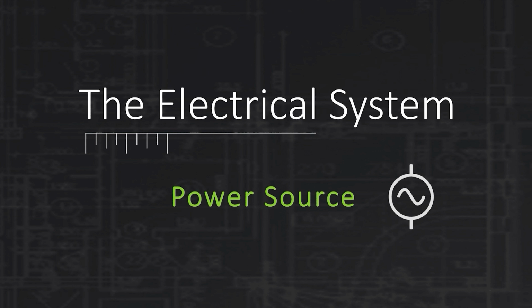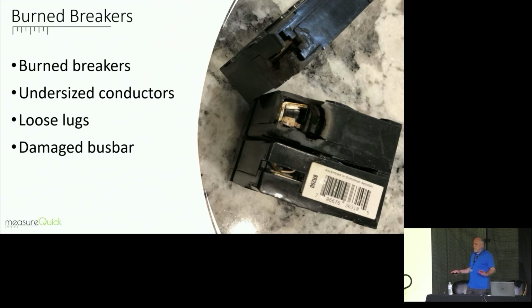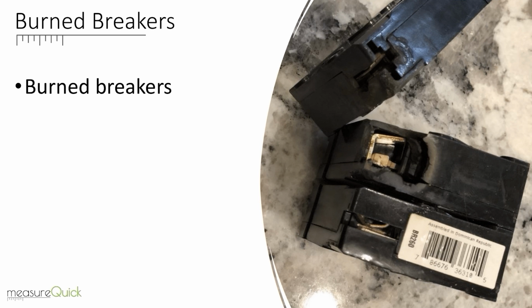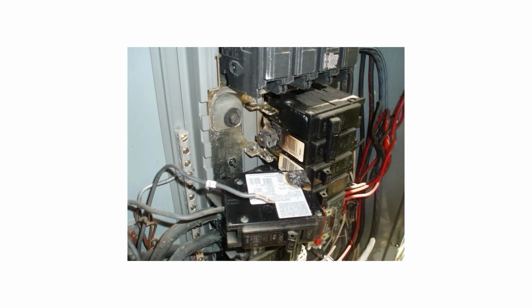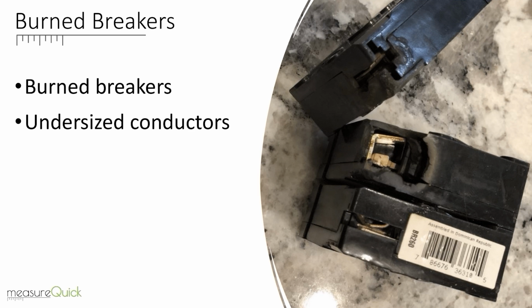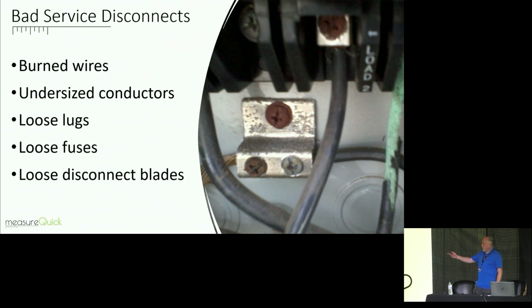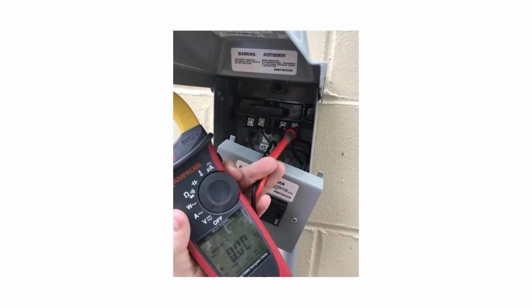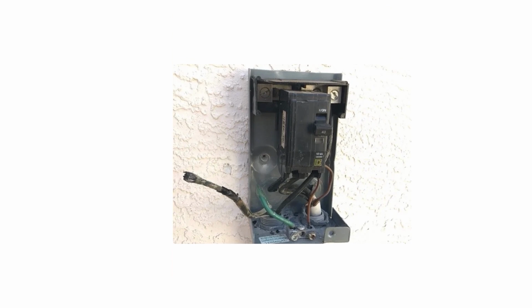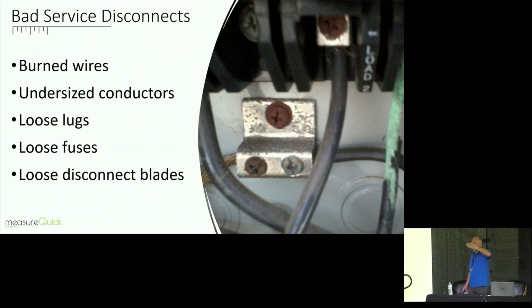Electrical system. I don't know how many times I've gone out and seen guys put in new systems and they don't check from the breaker box. I highly suggest, whenever you're doing a new system, pull the cover off the breaker panel, inspect the breakers, inspect the connections, look for undersized conductors, look for loose lugs, look for damaged bus bars on there, right? Service disconnects. When you touch a service disconnect, it should not be warm, right? One of the first things I do when I walk up and I lift the cover on a service disconnect is put my hand on it to see, and Joe will say, put my hand on backwards in case I get shocked on there, right? But the idea behind it is you're feeling the service disconnect to see if it's warm. It should not have any noticeable temperature, right?